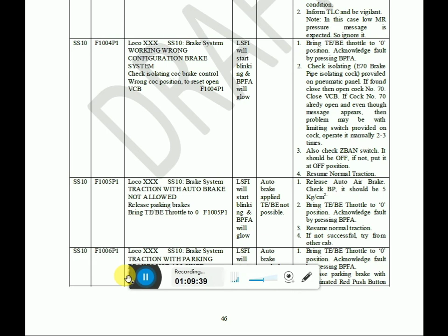LSFI will blink, BPFA will glow, and TB will not respond. So we have to bring TB handle to 0 and acknowledge BPFA. Ensure BP 5 kg per centimeter square. Ensure 70 cock in open position and ZBAN in normal position, off position. Even if 70 cock is in open position, if the message is repeating, operate a limiting switch 2 or 3 times for 70 cock.